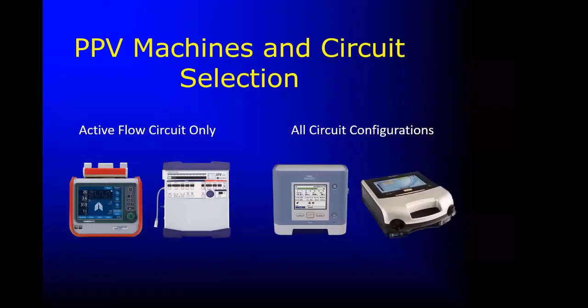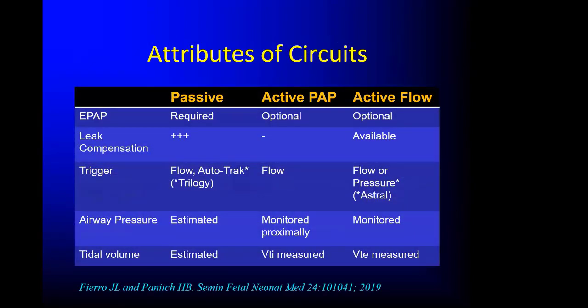Now, certain machines will dictate which circuit we use. So the LTV and the Hamilton only use that active flow circuit. The Trilogy, the Astral, the Evo can use a passive leak circuit, an active PAP circuit, or an active flow circuit. So you've got lots more choices when you use those types of ventilators. Most people use a passive leak circuit, and so I want to talk a bit about that, and I'll compare it to the other two circuits. So remember, all you have is a hole, and if you don't provide continuous flow past that hole, then depending on how far away that hole is from the patient's airway opening, you're adding dead space to the circuit.